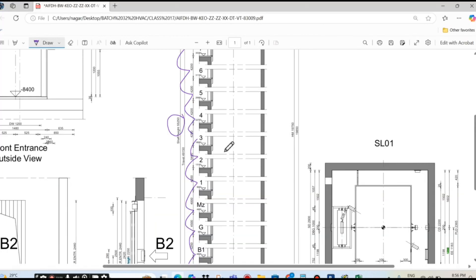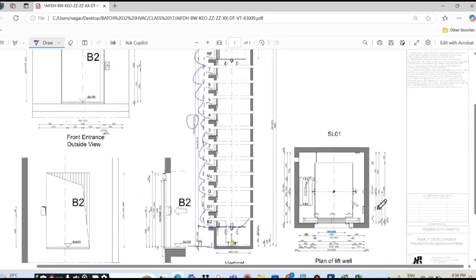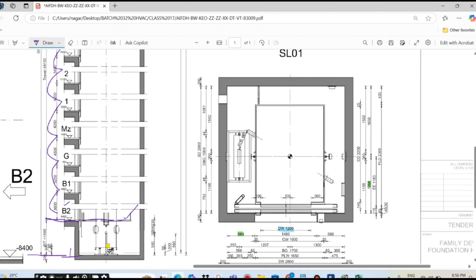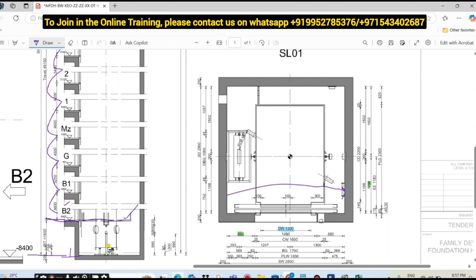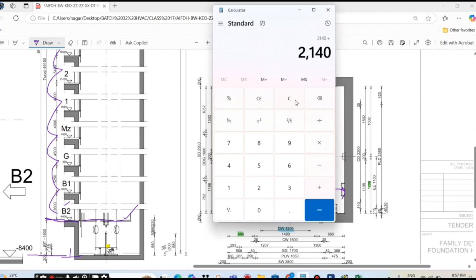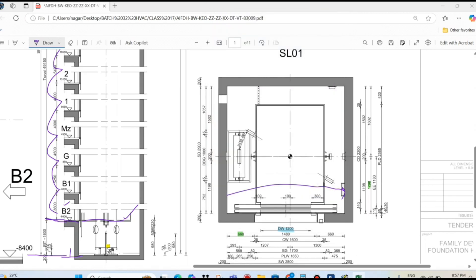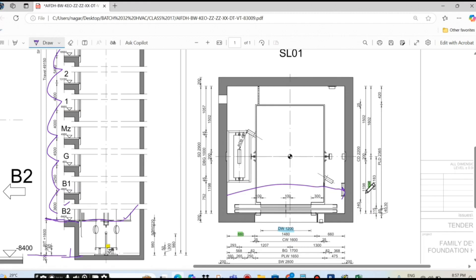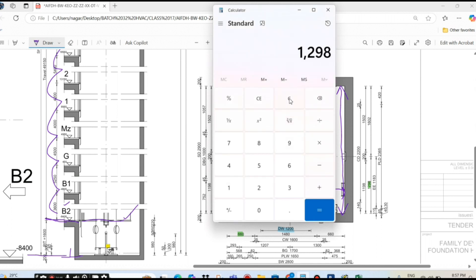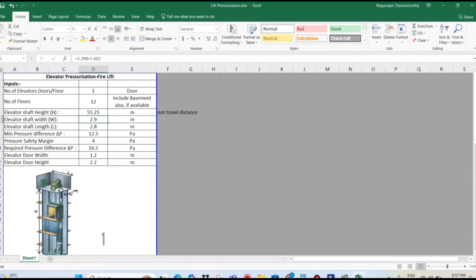Elevator shaft width. So we need to say the width here — you see the top view. The elevator shaft width is from here to here, the internal I need to consider. So if you see the dimension: 660 plus 1480 plus 660, that is 2.8 meters. So for the elevator shaft width and length, we need to consider the dimension: 1298 plus 1602. So 2.8 meters this side and 2.9 meters this side. So both width and length, we have to consider 2.9 meters and 2.8 meters.